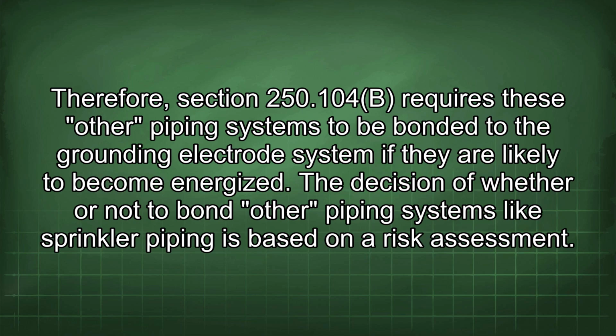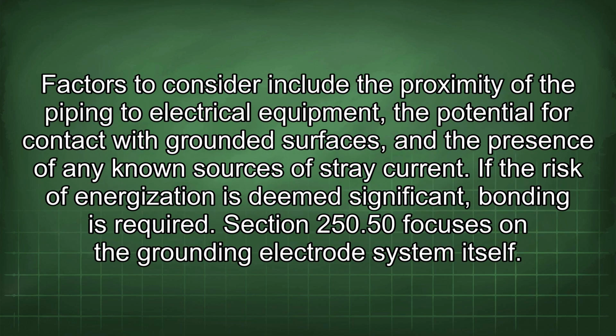250.104(B) requires these other piping systems to be bonded to the grounding electrode system if they are likely to become energized. The decision of whether or not to bond other piping systems like sprinkler piping is based on a risk assessment. Factors to consider include the proximity of the piping to electrical equipment, the potential for contact with grounded surfaces, and the presence of any known sources of stray current. If the risk of energization is deemed significant, bonding is required. Section 250.50 focuses on the grounding electrode system itself.